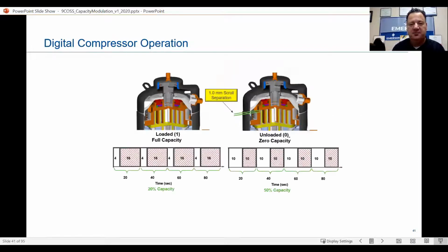Can't emphasize that enough. So here's a digital compressor operation. On the left-hand side, we're showing it loaded. On the second picture on the right is unloaded. So in refrigeration, the way the digital works is it's in 20-second increments, okay? So in other words, this is showing that we're loaded for 4 seconds. In other words, we're unloading for 16 seconds, loaded for 4 seconds, unloading for 16 seconds. By the way, never shutting off. Okay, we're just separating those scroll sets, that 1 millimeter that we talked about earlier.